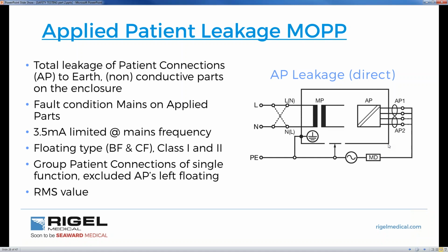The reason why you put mains on applied part, yes, it is to prove the isolation, but also it's to prove that whoever has a patient connection on them, let's say a guy is lying in a bed, if he happened to come in contact with any hazardous voltage source or current source, then he should remain floating. So he should remain isolated because of this barrier that is internal within any medical device from protective earth. So that's the purpose of doing mains on applied part testing. It's not called mains on applied part testing within 62353, but effectively that's what we do. We put a potential in there that is isolated.